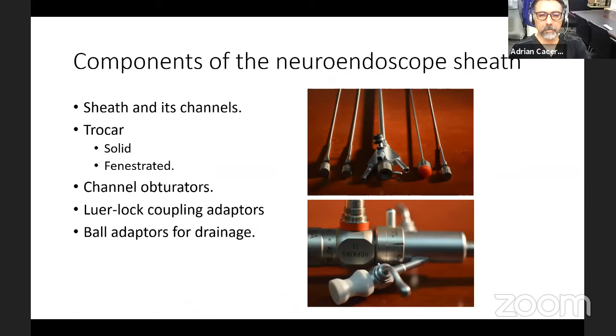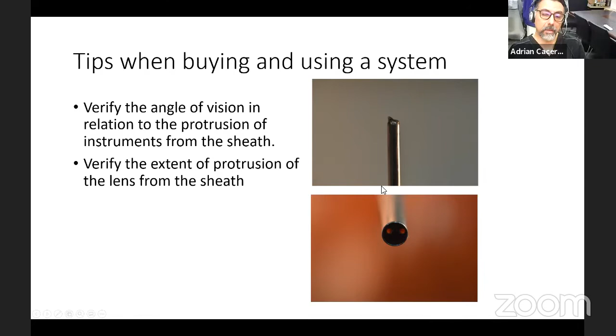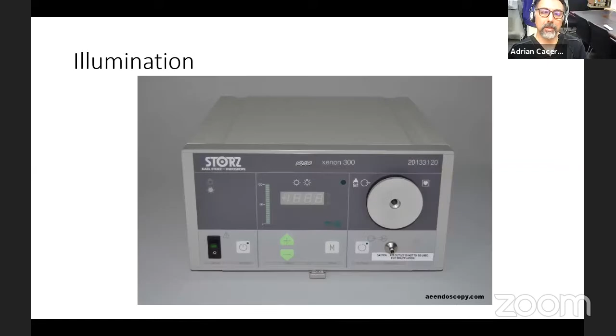Always, whenever you're starting an endoscopy, be mindful that whenever you're using a 0-degree angle, there's no protrusion of the lens through the sheath, whichever sheath it is, so it's flat. But whenever you're using a 30 or more degree angle endoscope, in order for you to have this field of vision, the tip of the lens will protrude, and sometimes instruments that come on the side will not be seen in your field of vision until they're already 1 centimeter out. So you should always play with your endoscope beforehand.